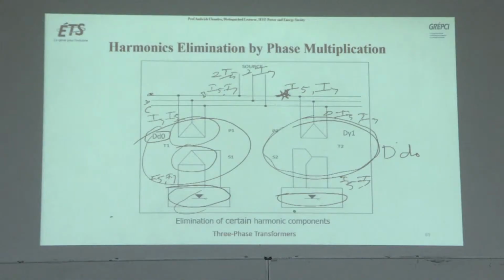So we know that if we have similar transformers for similar types of load, it will generate a lot of problems. That's why we take the example of a DY1 transformer. Primary is delta, secondary is star, and there is one, which means the secondary voltage is lagging behind by 30 degrees with respect to the primary voltage. So will it be able to cancel 5th, 7th harmonic or not? This is what we have to analyze. An engineer has to see this.